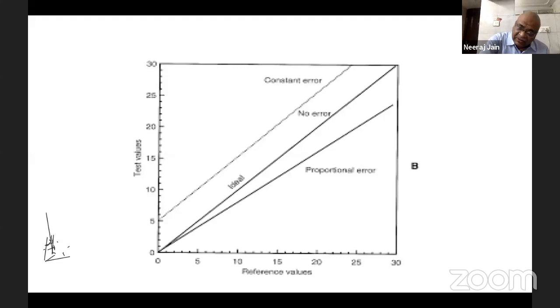Now see the line below this ideal. The difference between the ideal and this line is increasing with increasing concentration. This is called systematic proportional error. So when we are comparing two equipments, we have to see this. And there is a calculator available on the Westgard website. You can submit the data of your two machines on that, and it gives you a graph like this, and one R2 value. This is called the correlation coefficient. If it is more than 0.9, there is a good correlation, and if it is more than 0.95, this is excellent correlation. It should be as close to 1 as possible.